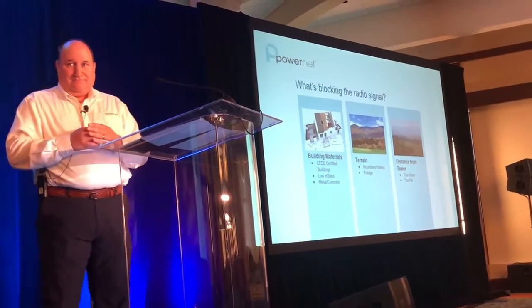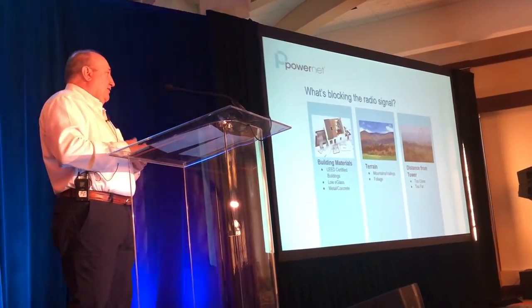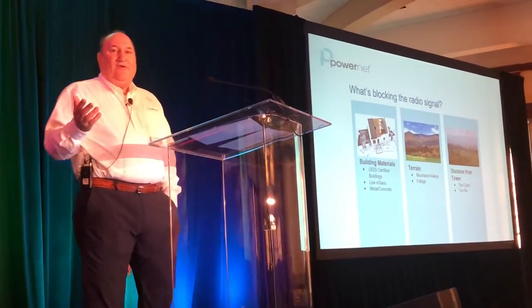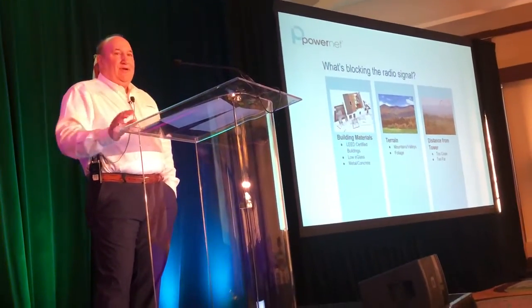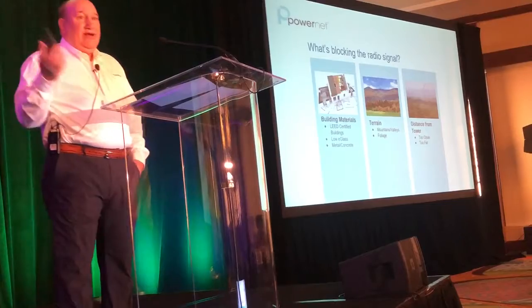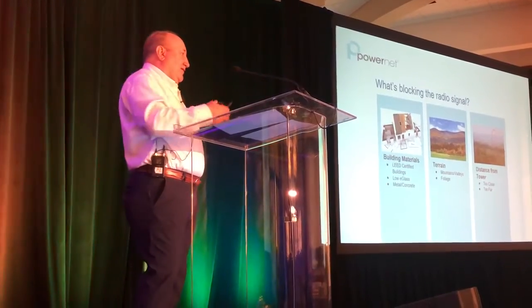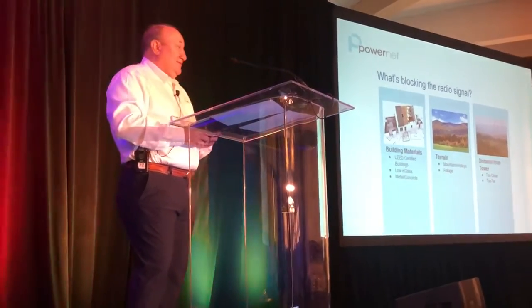But imagine a scenario like this, which we had last year, a customer that we were doing a lot of technology for, a 160,000 square foot building. Outside the building, the signal was a negative 48. What that means is it was a perfect signal. It was incredible. Should have had no problem with the building. They were getting close to CO. As the fire inspector walked through the building, his radio kept going off. So he tried to key and talk to the tower. He couldn't talk to the tower. He tried to key and talk to his crew, and he couldn't. And so he kept walking the building. He thought maybe it was just something odd with his radio. But he had no area inside the building where he could communicate back to his dispatch center.